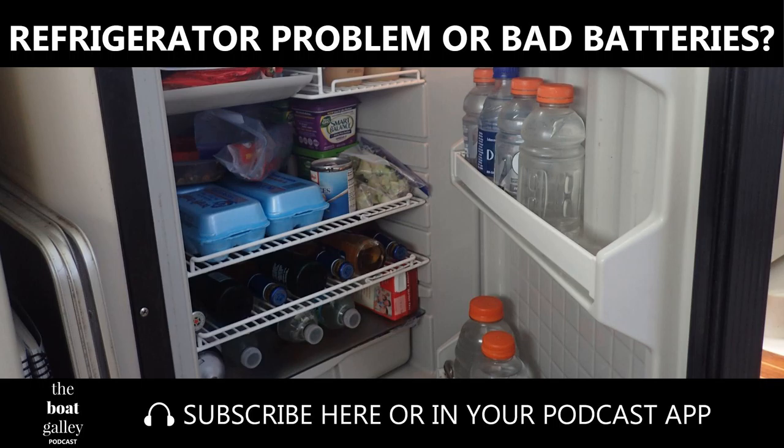The refrigerator had been working just fine, and the weather hadn't suddenly turned hot, nor was there any obvious explanation for the problem. So we assumed that the refrigerator needed to be recharged. We read up on the procedure, borrowed gauges, and proceeded to do it. No improvement. We then decided that the problem was beyond us and called in the refrigerator repairman. He figured that we had added too much refrigerant, so evacuated it all and then recharged it, leaving us with instructions on how to let out a tiny bit more gas if it still wasn't cooling right. And he told us to allow 24 to 48 hours for everything to settle out.